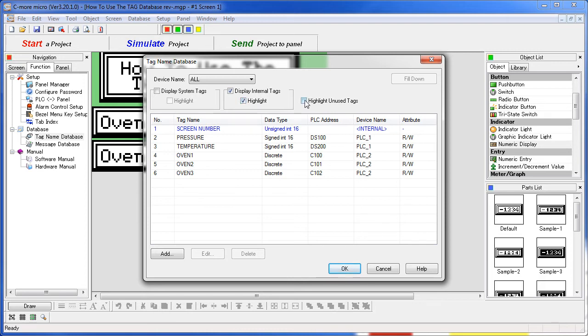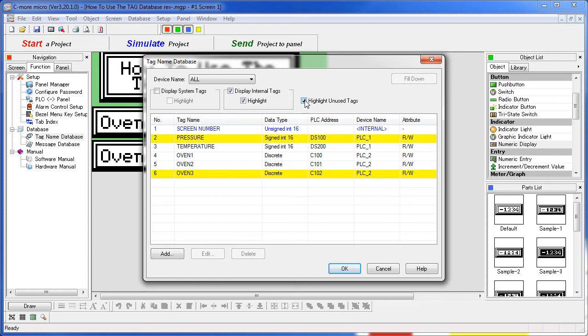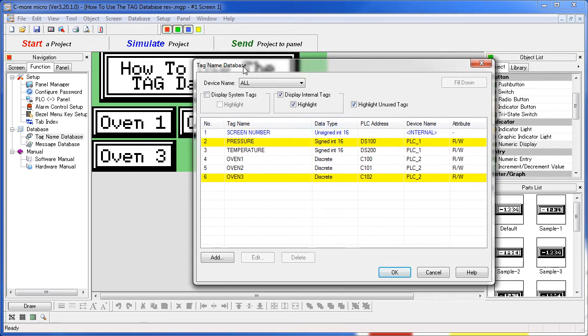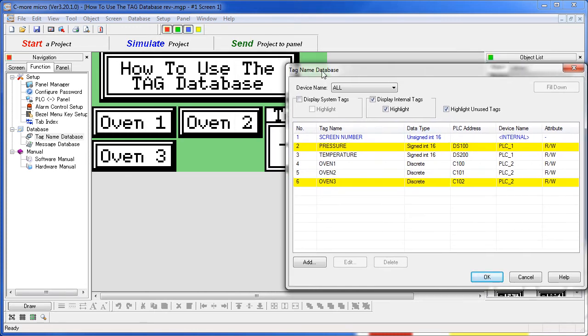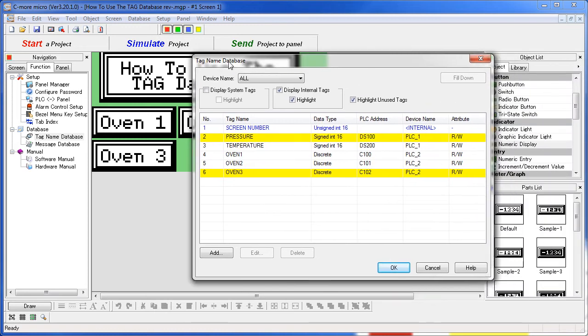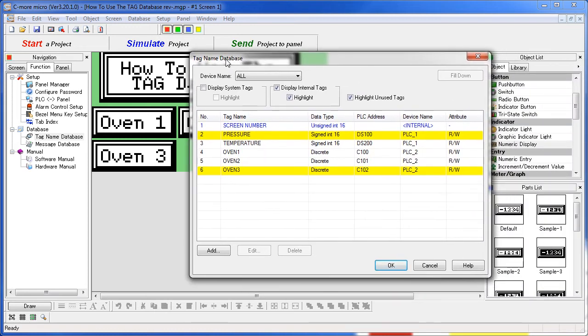And you can highlight unused tags which is a real quick way to find out if you have any extra tags in your project. For example, we see that Oven 3 is unused but we have an Oven 3 push button so that tells me there is probably an issue with my project somewhere that I need to go debug.